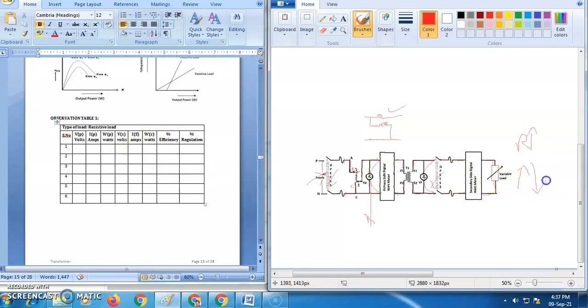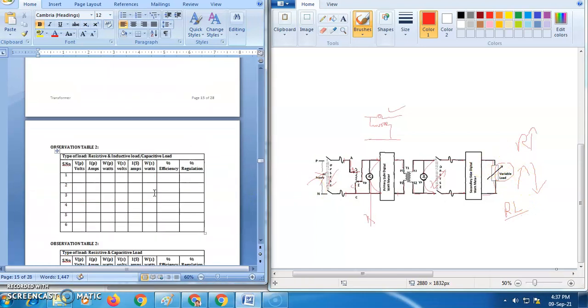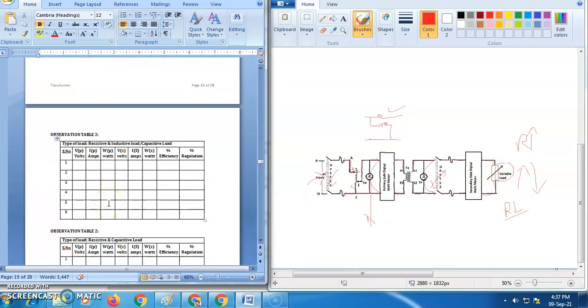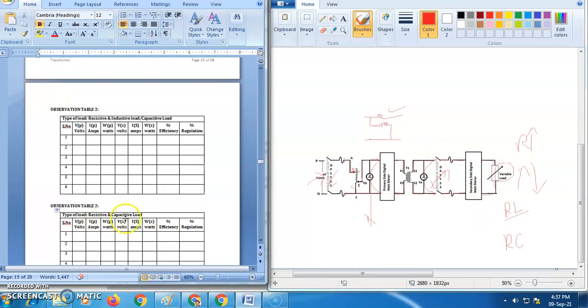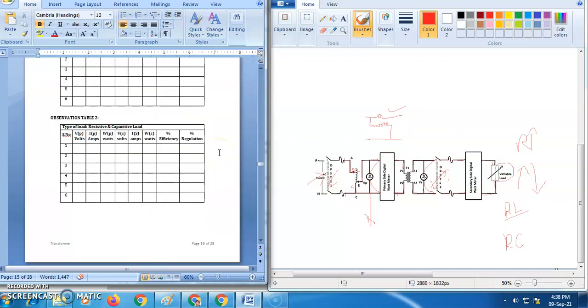And after that you can reduce this resistance value, and you can open the DPST2 switch and you can replace this resistance with resistance and inductive load, RL load. And once again you need to repeat the same, and that should be recorded in the next table. And very next, once again you need to minimize all the loads and open the DPST2, and once again you connect RC loads, right? So once again you repeat the same procedure, and that should be recorded in the last table, right? So now all these three things should be repeated up to the rated current values. So that is very important.